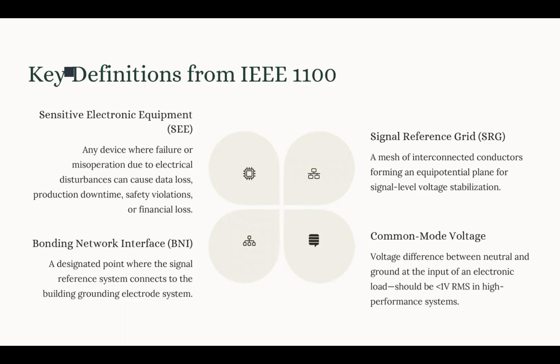For example, data servers, PLCs, SCADA systems, medical imaging equipment, broadcast transmitters, and avionic systems are very sensitive to those disturbances and the loss of power quality. Now, IEEE 1100 recommends clean power, which means voltage regulation within ±5% and THD less than 5%. It also recommends low noise grounding and zone segregation to make sure we are meeting the proper criteria for those sensitive devices.